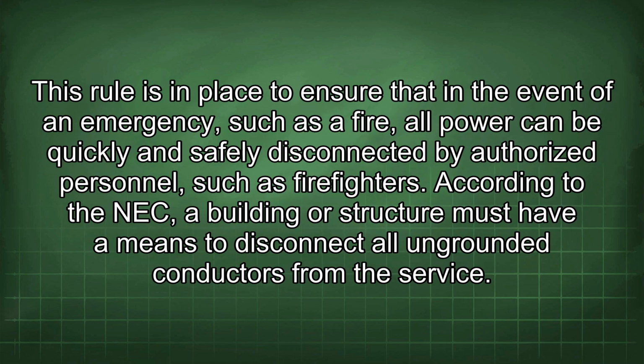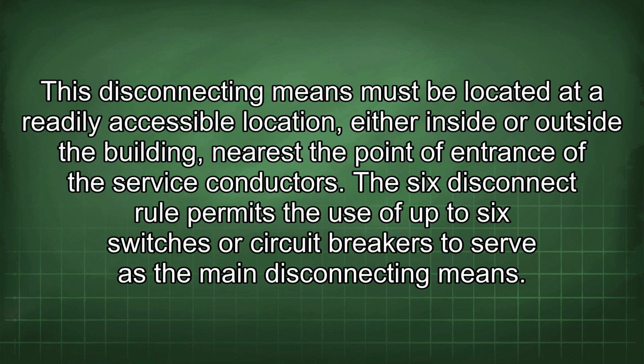This rule is in place to ensure that in the event of an emergency, such as a fire, all power can be quickly and safely disconnected by authorized personnel such as firefighters. According to the NEC, a building or structure must have a means to disconnect all ungrounded conductors from the service. This disconnecting means must be located at a readily accessible location, either inside or outside the building, nearest the point of entrance of the service conductors.